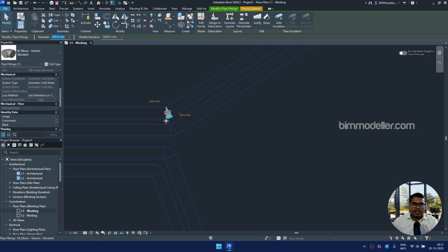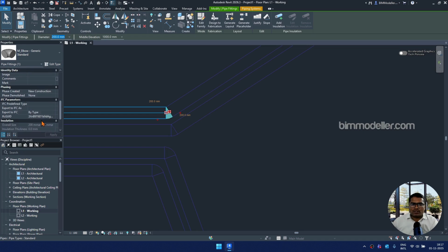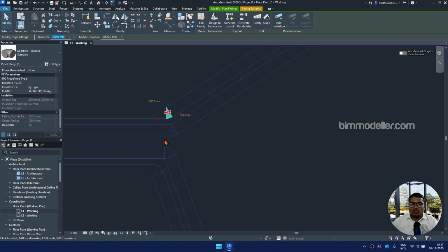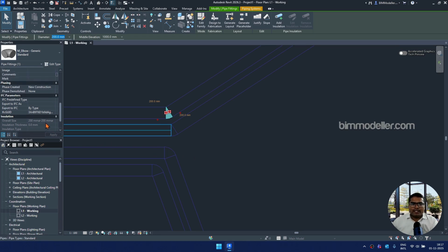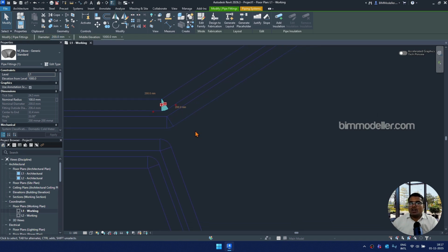And you see this pipework elbow, which is at a different angle than what is actually available in the market. That leads again to rework, or maybe a custom fitting needed for that fabrication part. So to avoid this, there are multiple ways that we can control it.